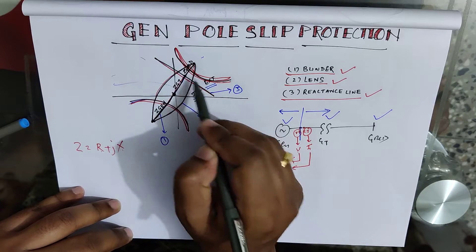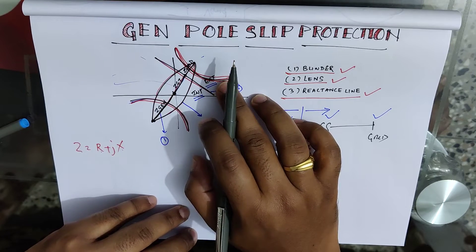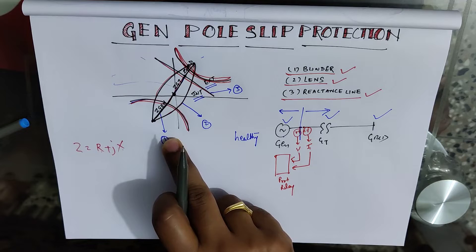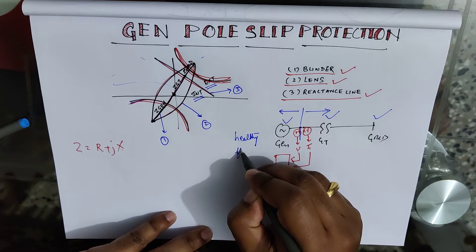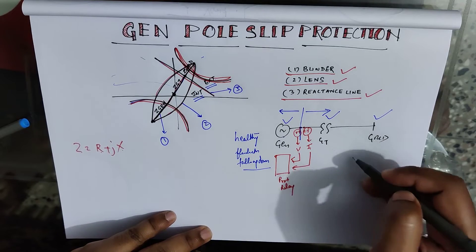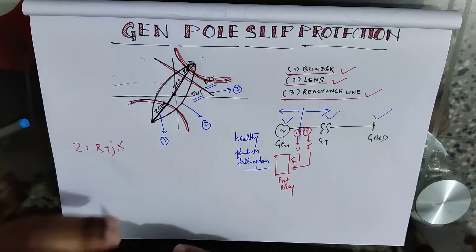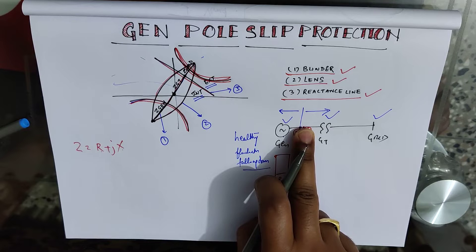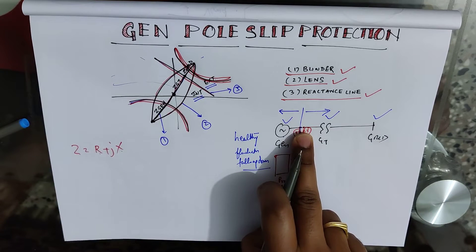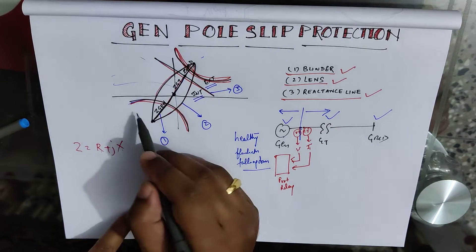The basic difference between internal and external swing: in an external swing, the generator terminal voltage remains healthy. But in an internal swing, the generator terminal voltage starts fluctuating or falling down. This happens because whenever there is a line fault or a heavy fault inside the power station, the excitation system — whose duty is to maintain voltage at the generator terminals — may not be capable of maintaining voltage due to heavy fault current.